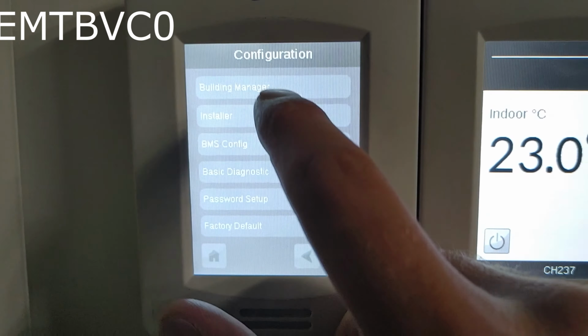Double click on our unit, go into the properties of the unit, selecting our 76,000 BTU indoor unit. Here we have default values for this unit, again for high, medium and low fan speed. We are interested here in manual setup.